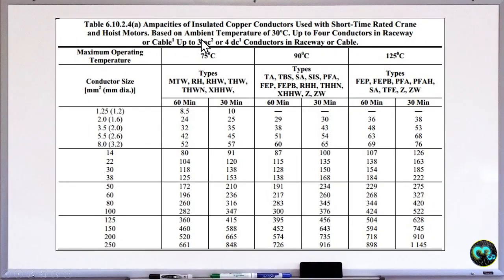Okay, so these are the wires to be used when it comes to mga hoist. So the crane and hoist motor, yan. So ito yung mga ginagamit. So it is different from the typical wire, kasi yung mga wire natin is dapat the minimum temperature rating is 75 degrees Celsius, the maximum is 125 degrees Celsius, and the largest size is 250 square mm, and the minimum size is 1.25 square mm.